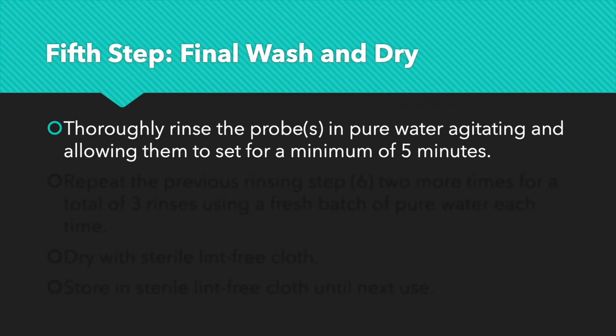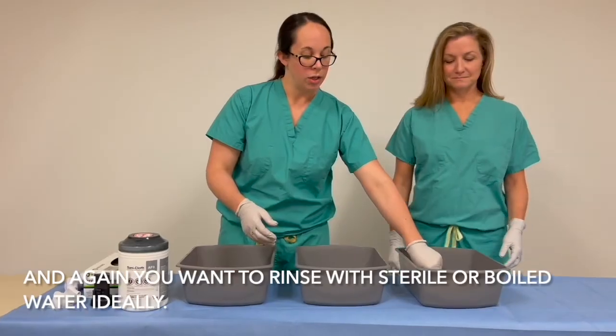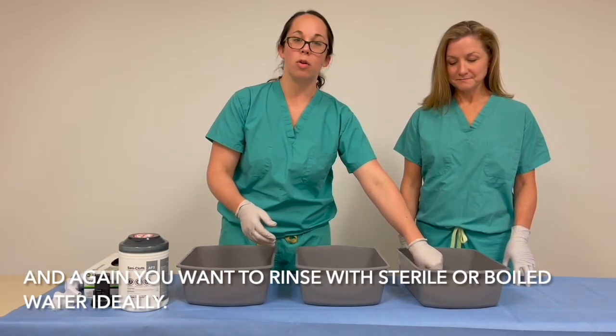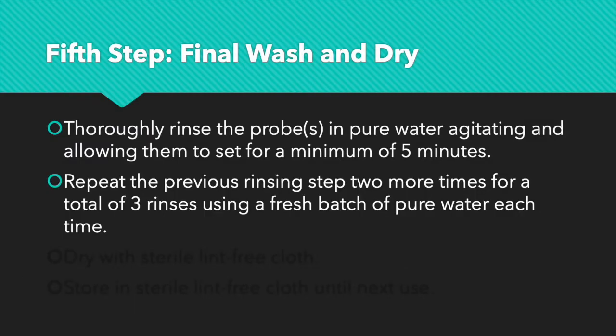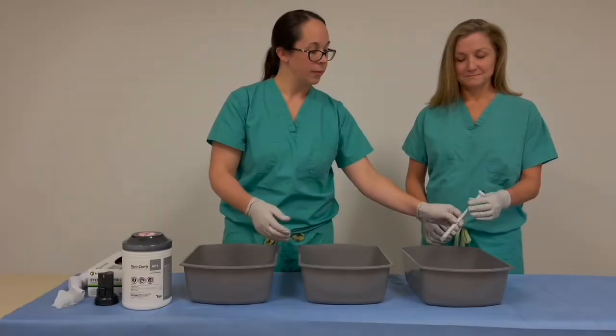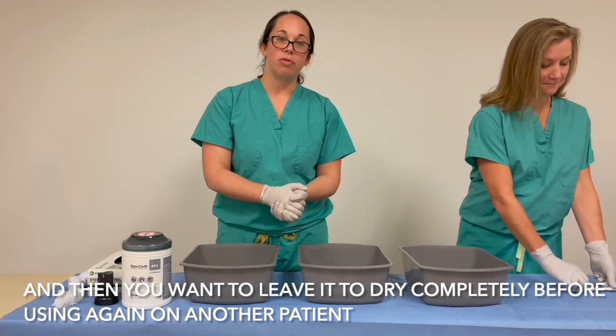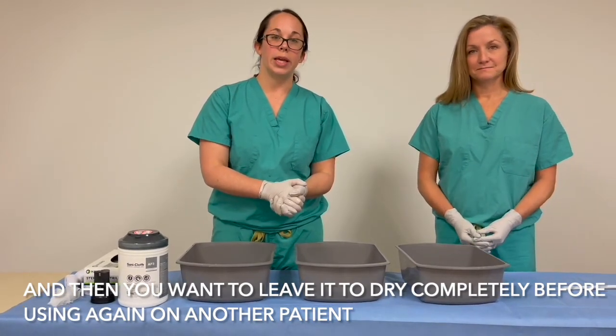The fifth step is the final wash and dry. Thoroughly rinse the probes in pure water, agitating and allowing them to set probe tip down in a cup of pure water for a minimum of 5 minutes. And again, you want to rinse with sterile or boiled water ideally. Repeat the previous rinsing step 2 more times for a total of 3 rinses using a fresh batch of pure water each time. And then you want to leave it to dry completely before using again on another patient.